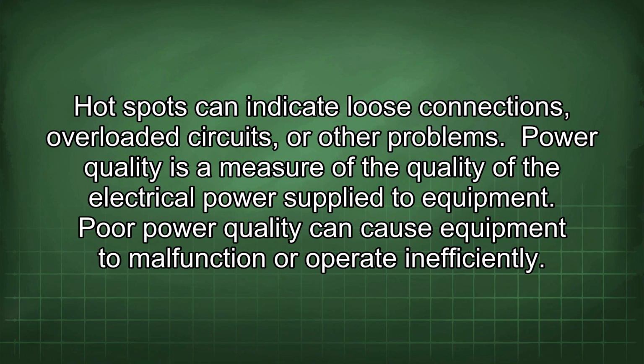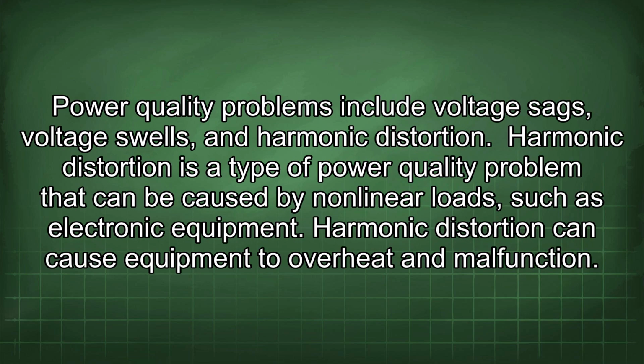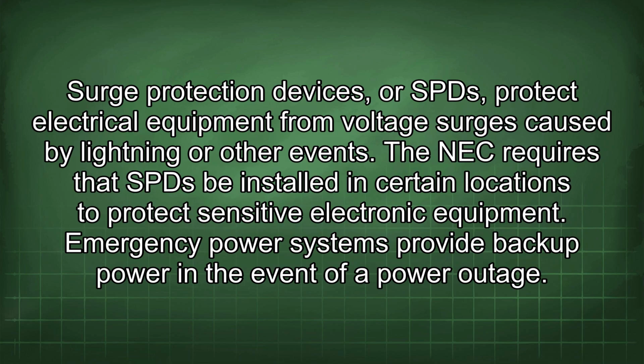Power quality is a measure of the quality of the electrical power supplied to equipment. Poor power quality can cause equipment to malfunction or operate inefficiently. Power quality problems include voltage sags, voltage swells, and harmonic distortion. Harmonic distortion is a type of power quality problem that can be caused by nonlinear loads, such as electronic equipment. Harmonic distortion can cause equipment to overheat and malfunction. Surge protection devices, or SPDs, protect electrical equipment from voltage surges caused by lightning or other events. The NEC requires that SPDs be installed in certain locations to protect sensitive electronic equipment.